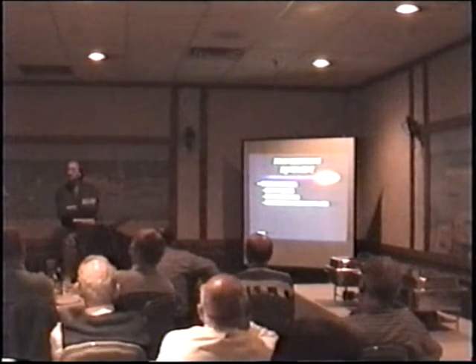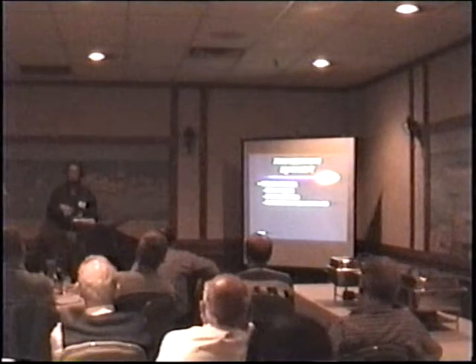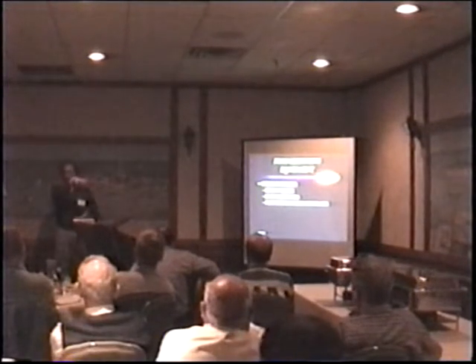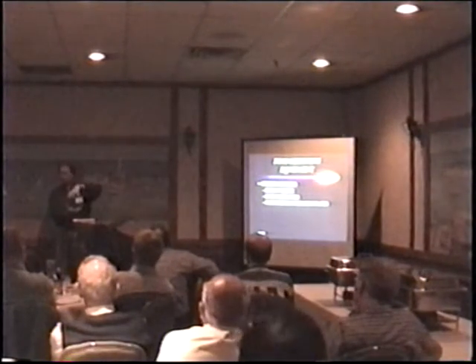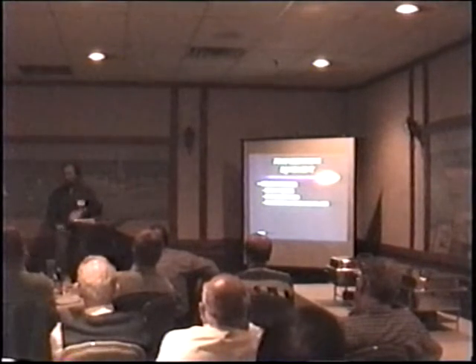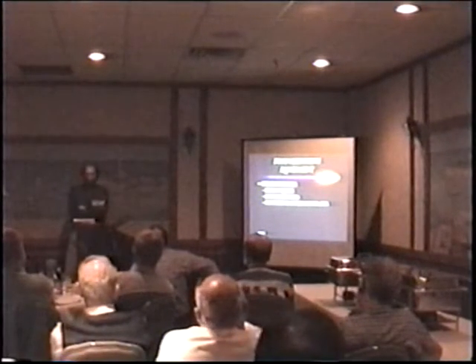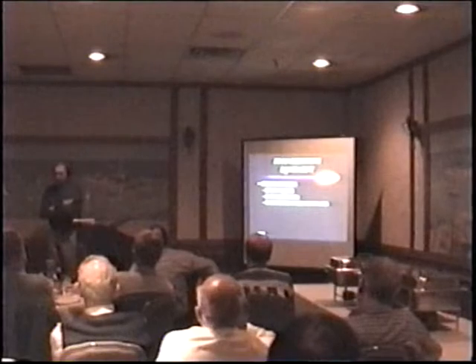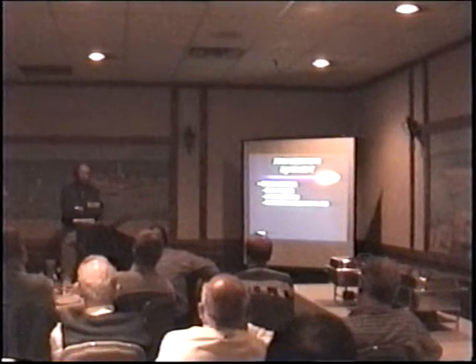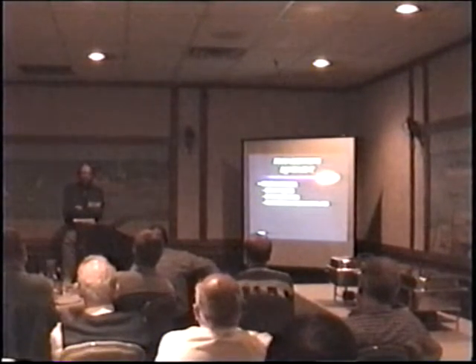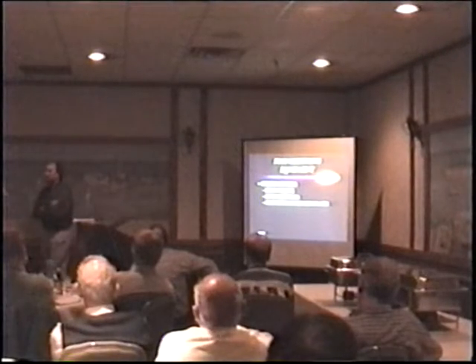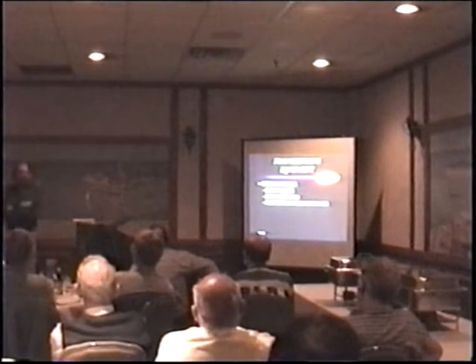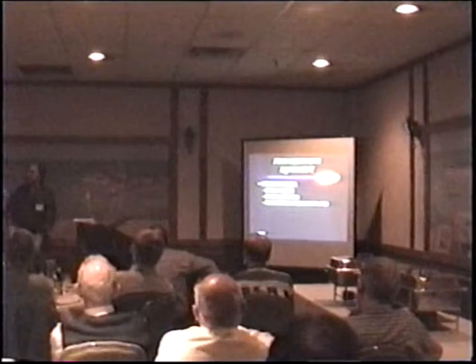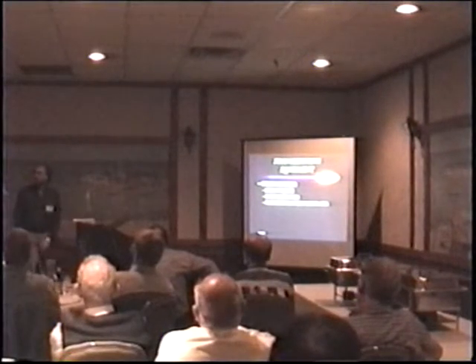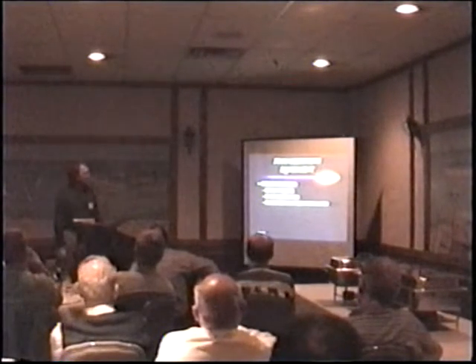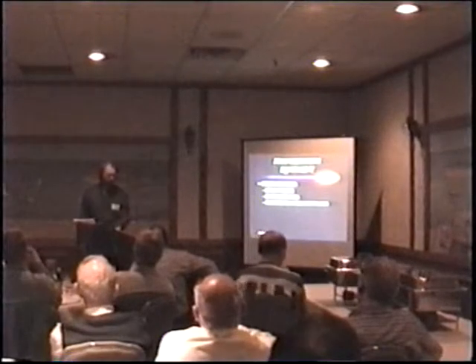They don't work well with AFFF because basically you have no bladder and you have a pressure proportioner on the top. The water just kind of comes in the top of the tank and forces the foam down and out from the suction tubes. Works well with protein foam, mainly because if you don't use the whole tank, protein foam is cheap and you haven't really lost anything. AFFF is a much higher price if you don't use the whole tank. Basically, you have water and AFFF mixed together. So, I've never really understood that system, but might as well put a bladder in.